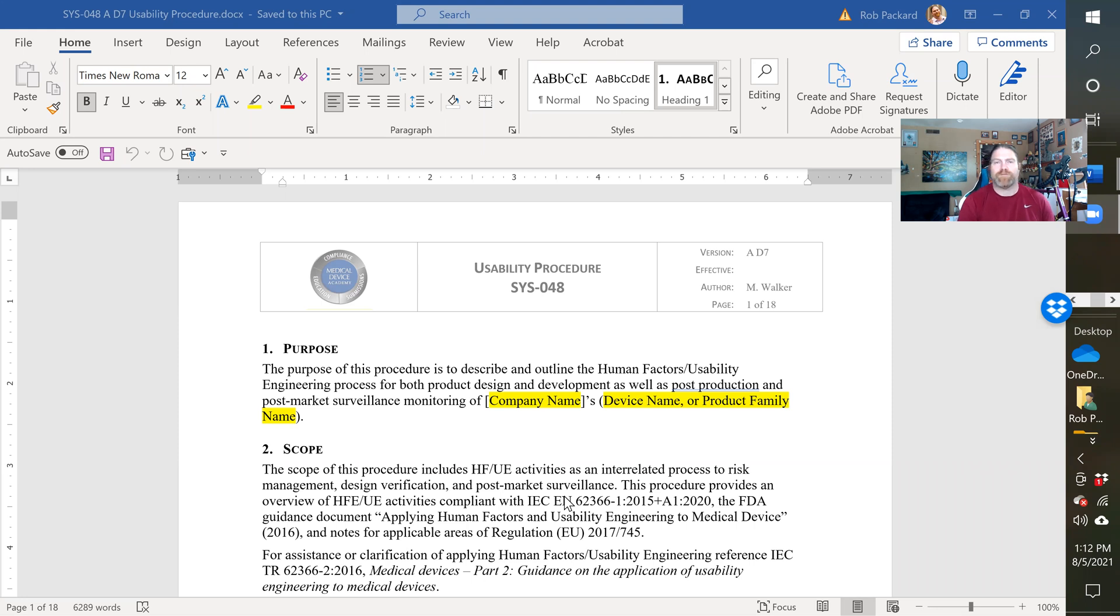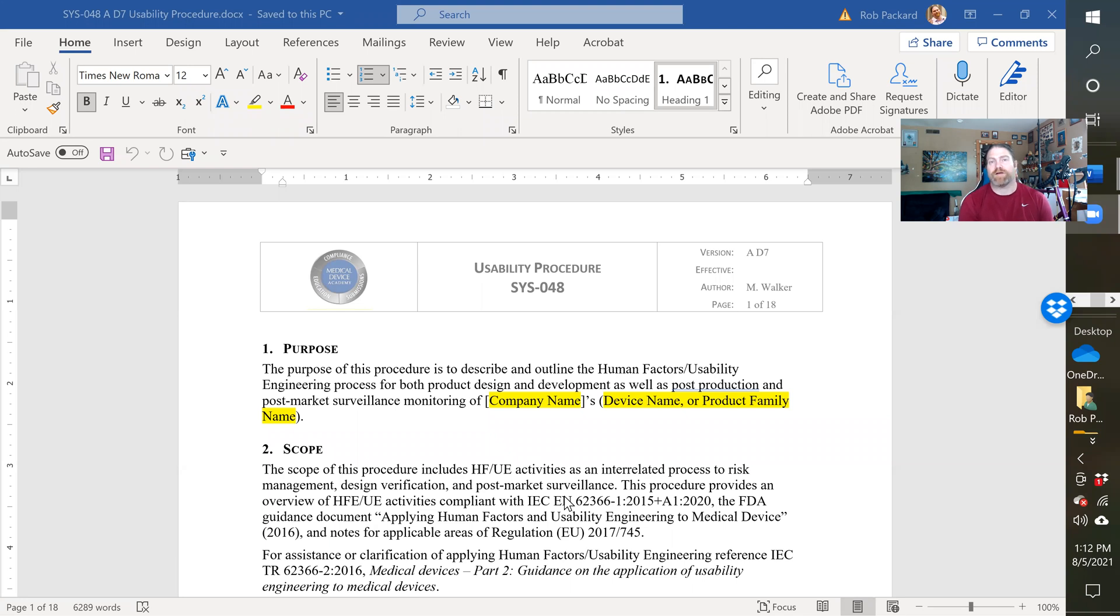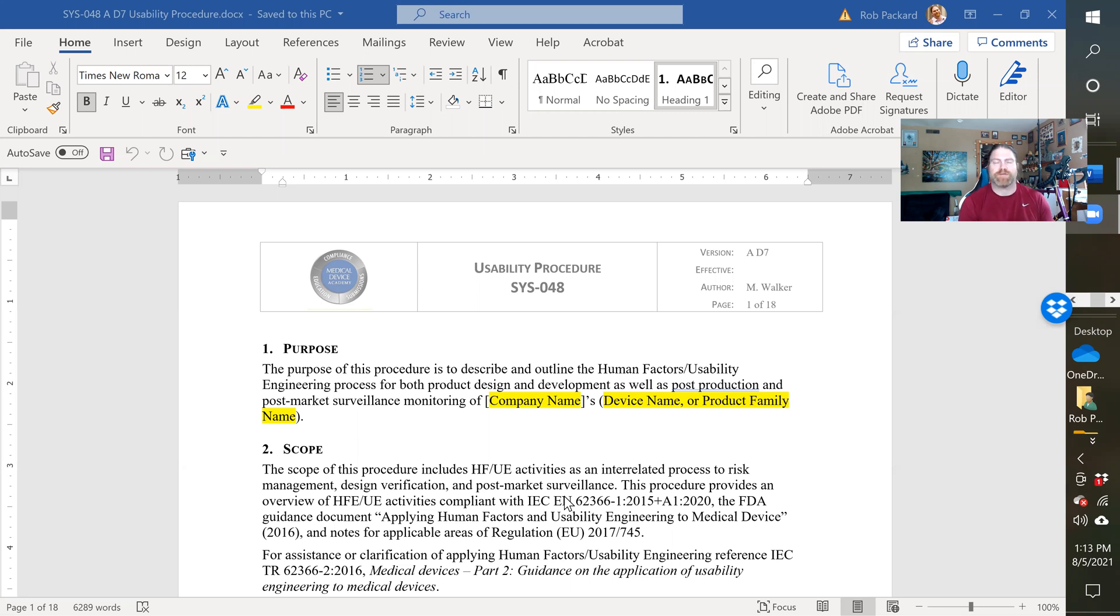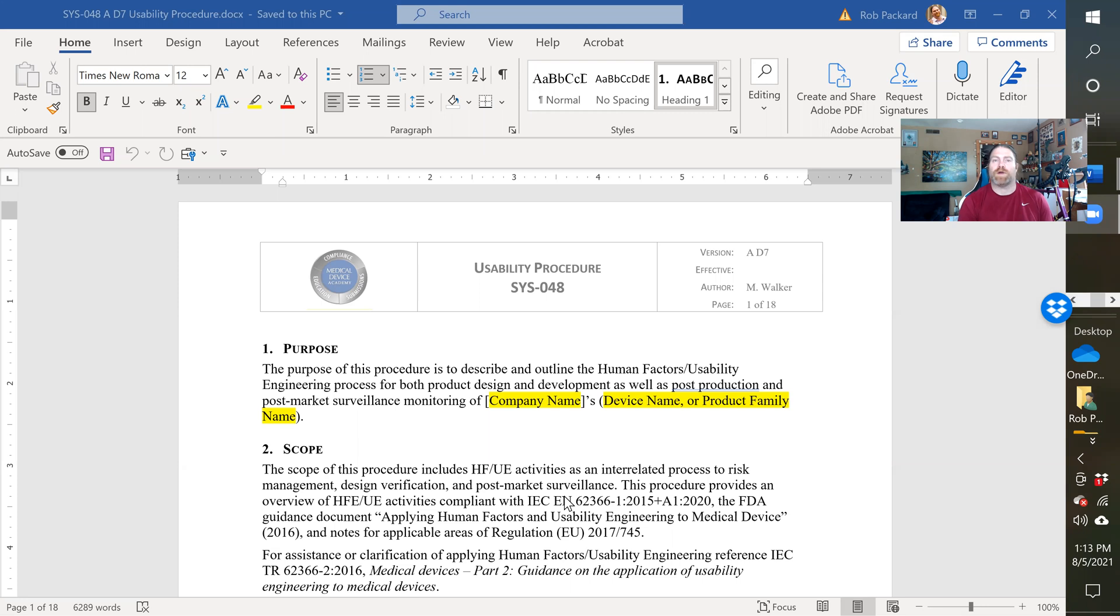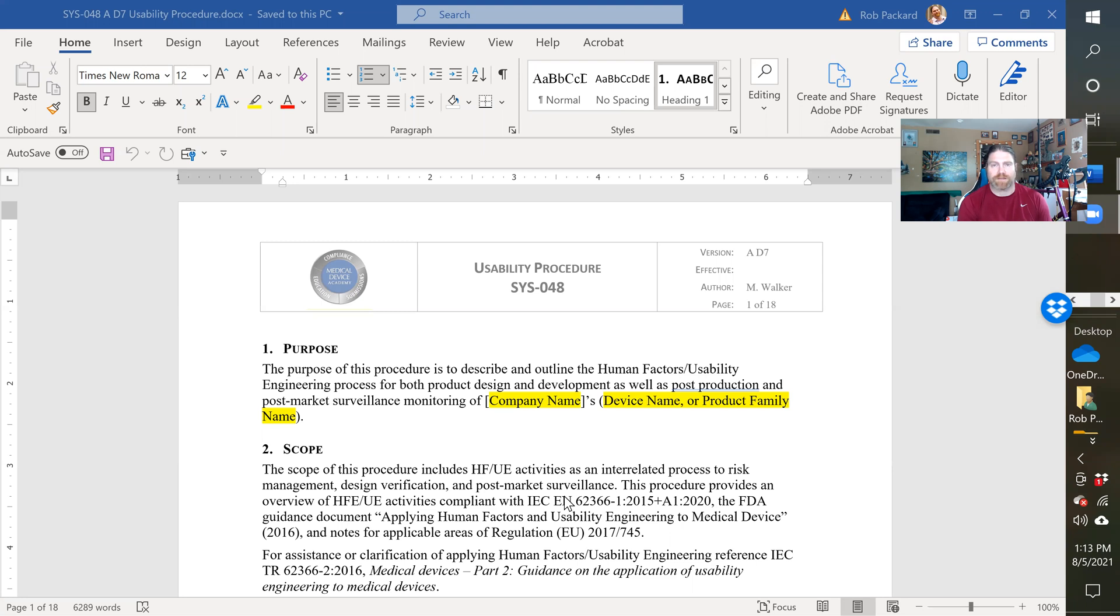We've been following FDA feedback on usability studies and the deficiencies that they identified during their review of a 510K submission, and one of the things that we identified that they're specifically looking for is a Use-Related Risk Analysis, or URRA. A lot of companies have a risk analysis, but they don't specifically have a document identified for Use-Related Risk. Usually it's incorporated with their regular risk documentation, which is perfectly acceptable, but if you want to separate it out, and if you're looking for what detail they want in that Use-Related Risk Analysis, we've provided a template for that in reference. The actual deficiency is an example. At the end of this is an appendix, so that might be helpful to you.